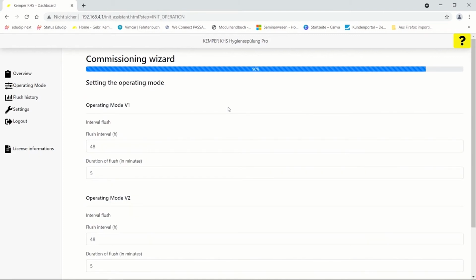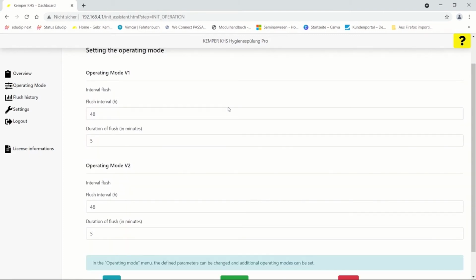The next point is to select the operating modes. Here we see that we have an interval flush, and the flush interval is preset to 48 hours, which means every second day. The duration for the flush of valve number 1 is preset to 5 minutes. Here we can change the presetting to be, for example, every 72 hours, which is every third day. And the duration should not be 5 minutes, it should be 3 minutes.